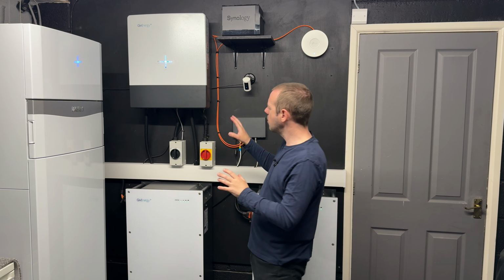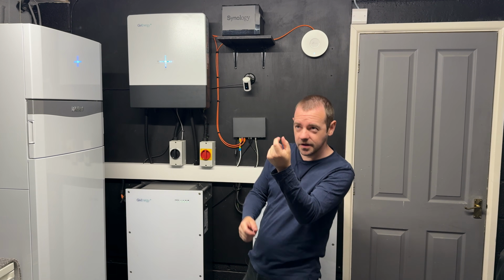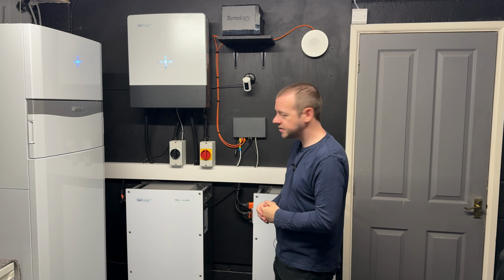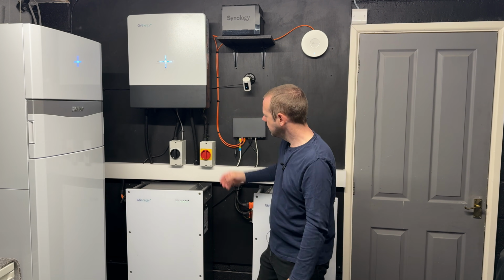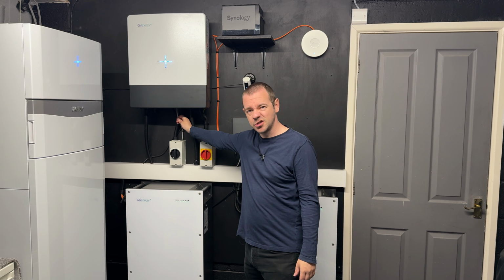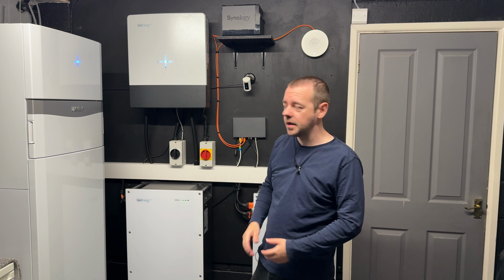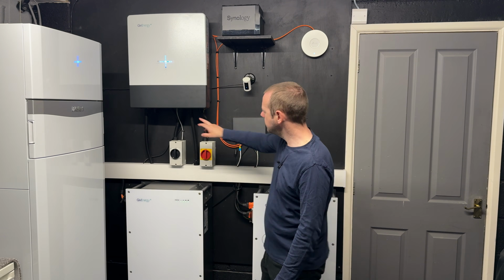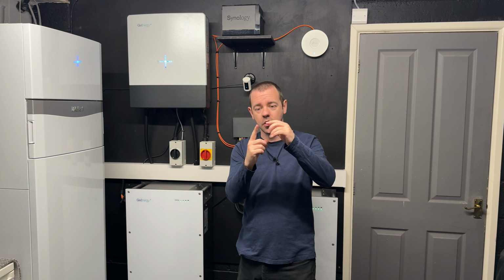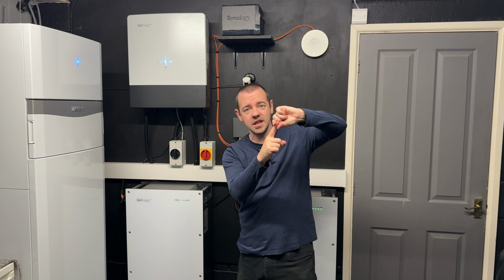So having someone come up and basically check every cable, is it still okay? Is there any signs of any thermal damage? I don't think it's a bad idea, because sometimes it's quite obvious. We have many occasions where a rodent of sorts, especially if the system's outside, has chewed through a cable, and there you go, problem is quite obvious. But sometimes the problem will be in here or in your consumer unit, and the cable has come loose, or they've pinched the sheathing, which doesn't immediately show itself, but eventually will do and causes problems.